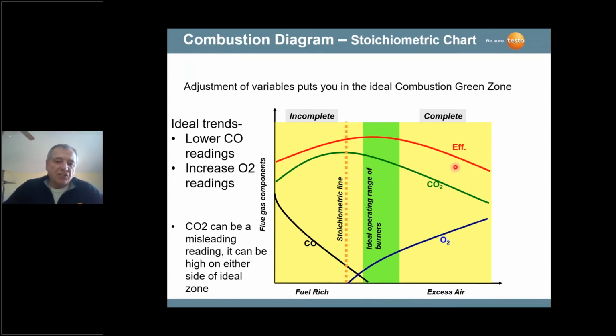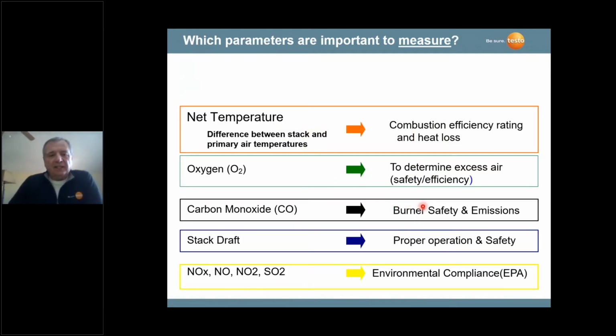So here's a relationship of the gases. Oxygen, stack temperature, and carbon monoxide are measured with sensors. Carbon dioxide is calculated based on knowing the fuel, and so is the combustion efficiency. It's calculated based on knowing the fuel and the oxygen. That's why when you turn a combustion analyzer on, you always need to select the correct fuel, because we not only are measuring CO and oxygen and stack temperature, but we're also calculating CO2 and efficiency, which requires the correct fuel to be inserted into the instrument.